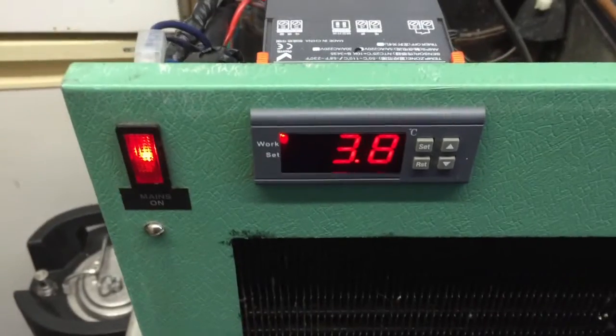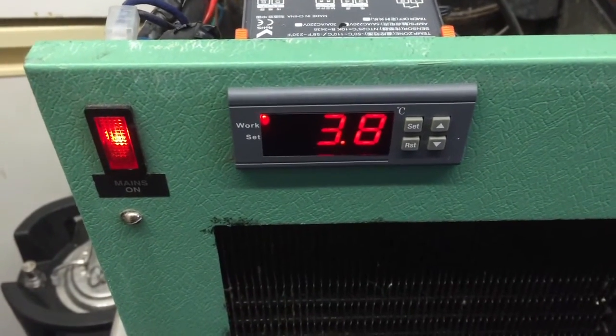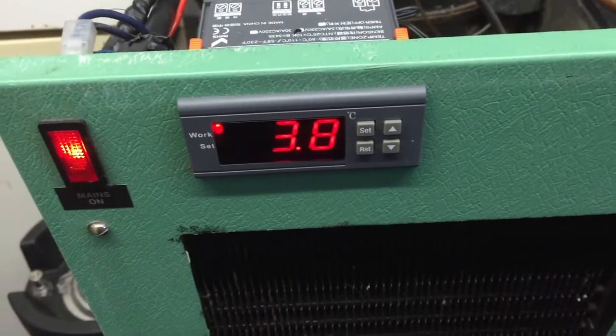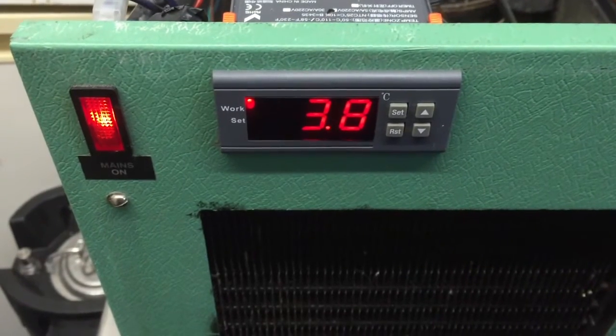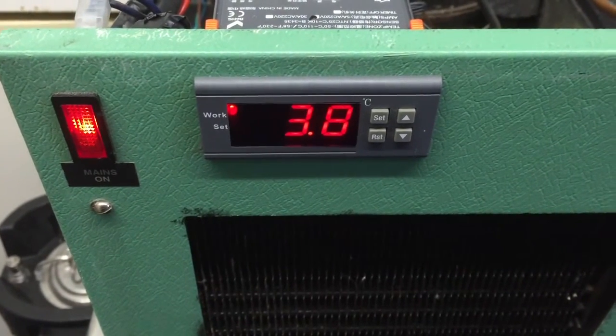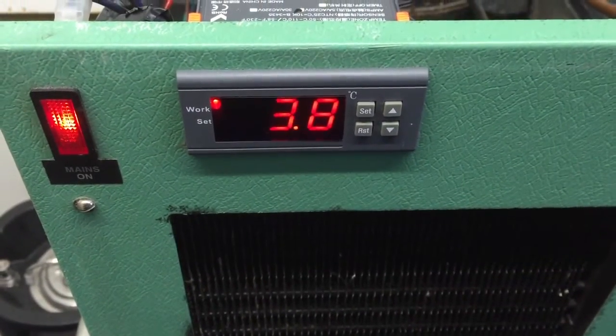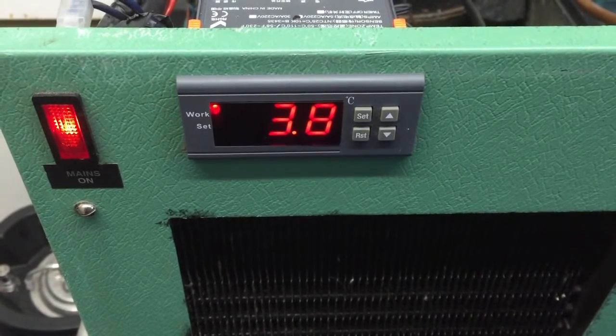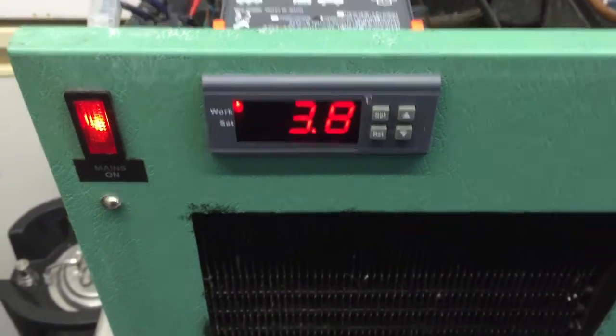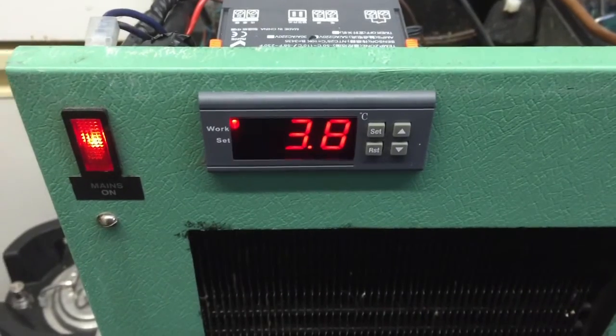And I've just got this one there, the temperature gauge. So we've just set it up to -2.5 to 6, which is the old thermostat setting, so we've gone as close as we can with this. It's just a matter of running it and seeing what happens, and then making any slight adjustments we need.